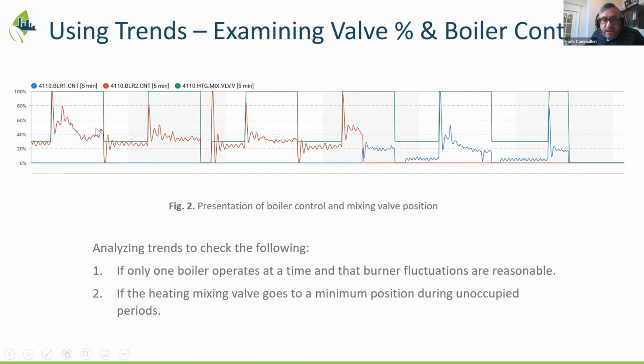The other thing we're looking for is whether the heating mixing valve goes to a minimum position during unoccupied periods, and that is this piece here. The valve position, this green line, during unoccupied periods is actually going to 30% in this case. Over here, when boiler number 2 is off, boiler number 1 starts to kick in and it's the only one operating, and burner fluctuations are reasonable. They're not crazy. They're not cycling throughout this whole graph. So again, this is further evidence of how you use trends and the importance of making sure your equipment is actually working as intended.